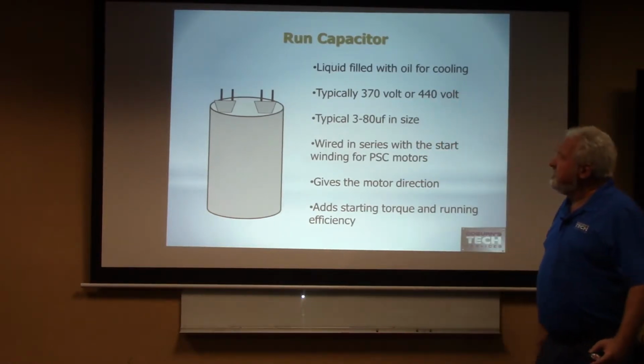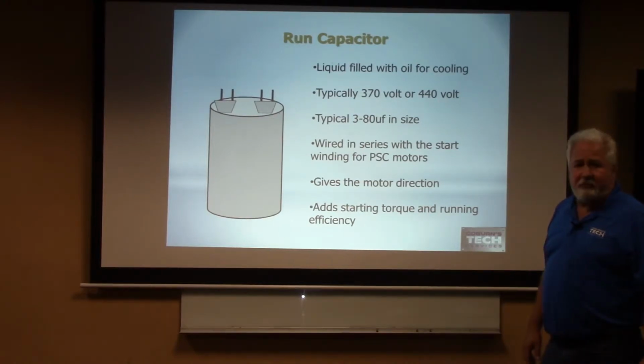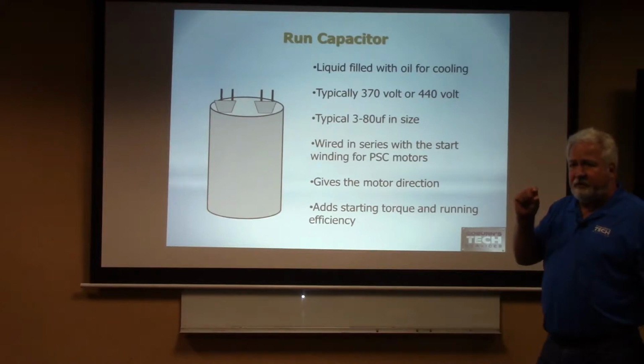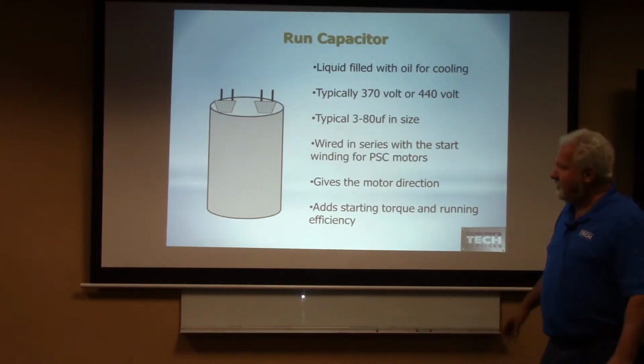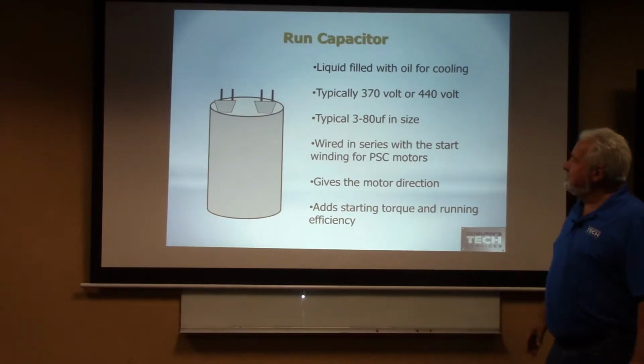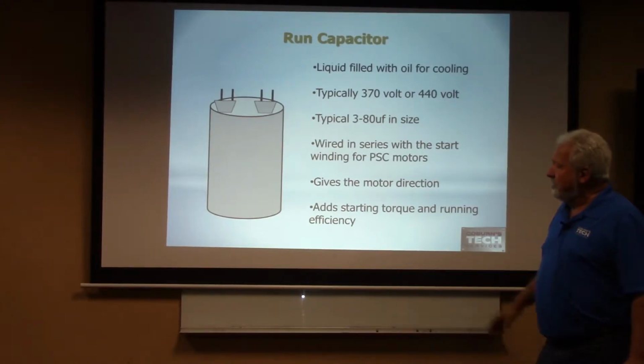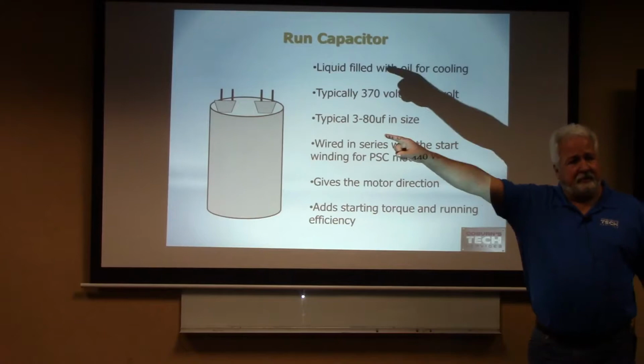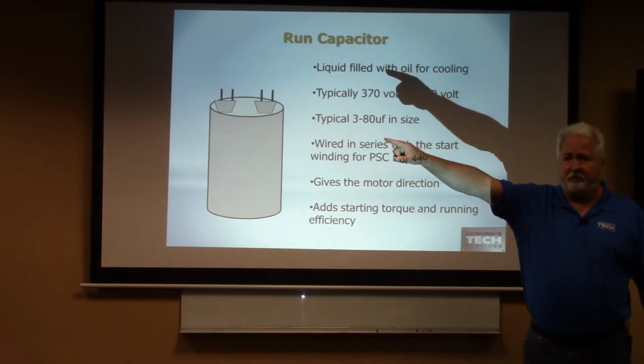Typically, we're 3 to 80 microfarads. You know what a microfarad is? It's a little bitty farad. Wired in series with the start winding of a PSC motor. It's wired in the start winding of that motor. It gives the motor direction. It tells it this is the way you have to go.